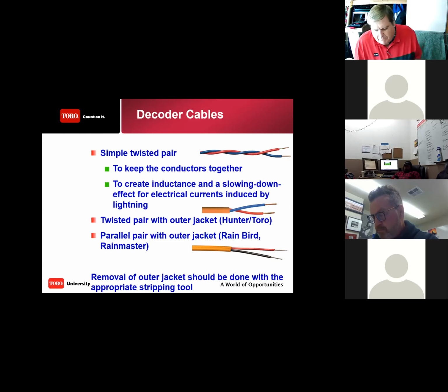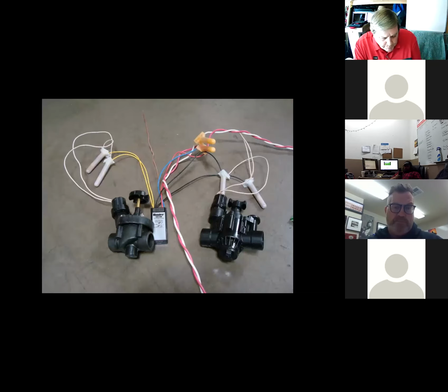So maybe a twisted pair would be a slight bit better, but negligible at that. Whatever wire you use, it works fine either way. Twisted pair or parallel, either way works. If you've got a project that's specified to have Toro wire, then use the Toro wire. For Rain Bird wire or Rain Master wire, those brands are specific for the brand, and if that's what the specification calls for, by all means use it. Here's an example of twisted pair.